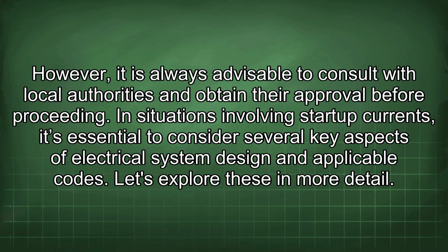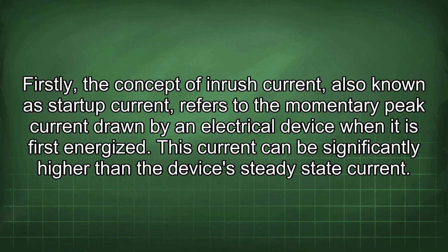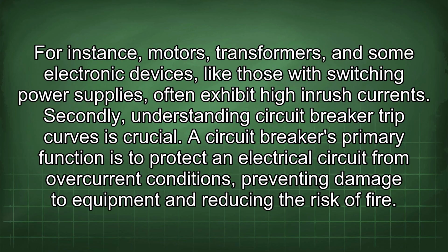However, it is always advisable to consult with local authorities and obtain their approval before proceeding. In situations involving startup currents, it's essential to consider several key aspects of electrical system design and applicable codes. Let's explore these in more detail. Firstly, the concept of inrush current, also known as startup current, refers to the momentary peak current drawn by an electrical device when it is first energized. This current can be significantly higher than the device's steady-state current. For instance, motors, transformers, and some electronic devices, like those with switching power supplies, often exhibit high inrush currents.